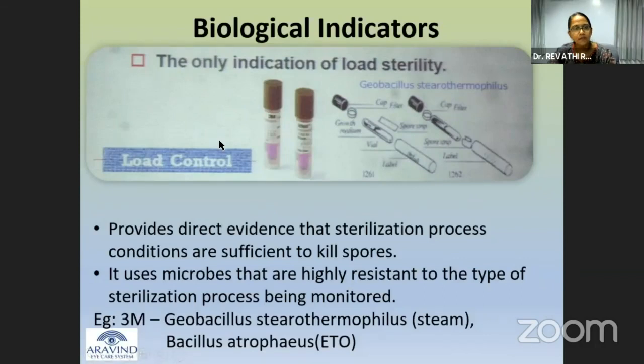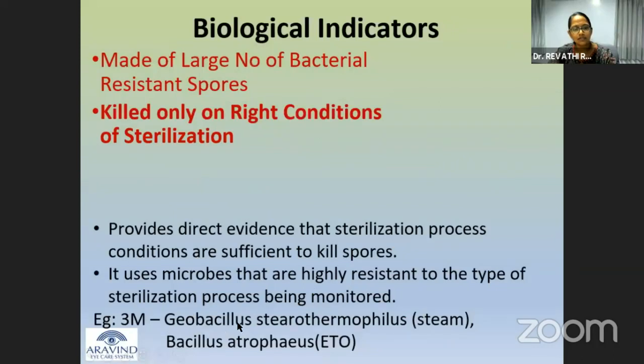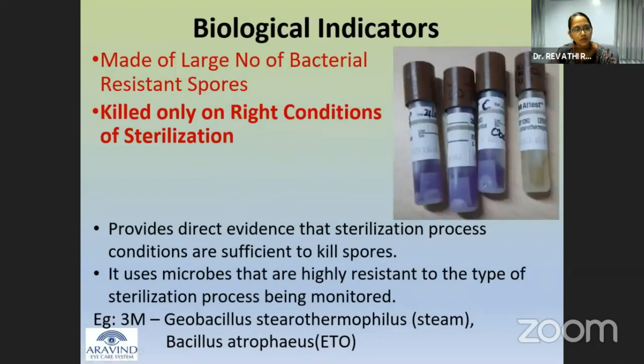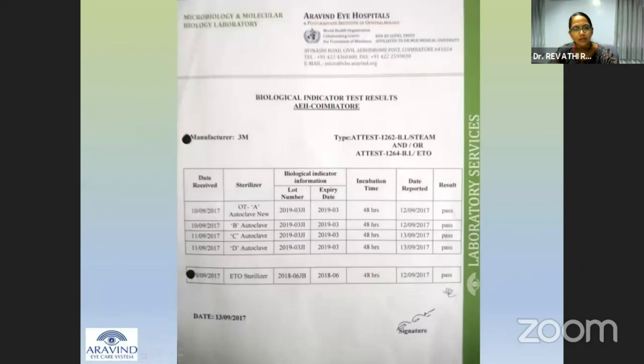The biological indicator has Geobacillus stearothermophilus for steam, and for ETO it is Bacillus atrophaeus. So the tubing contains a large number of bacterial, heat-resistant spores, which are killed only under the right conditions. After the tubes are placed in the autoclave, if the right condition has been met, once they are sent to the lab and incubated, it will remain the same color. If the organisms are not killed and the right condition hasn't been achieved, you will see, as it appears in the 4th tubing, that the color will change to brown. That means the autoclave has not run to the proper parameters. So we need to be careful about that.